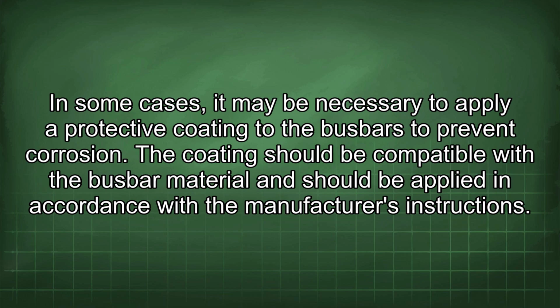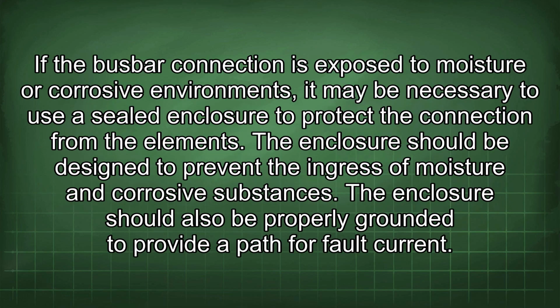In some cases, it may be necessary to apply a protective coating to the busbars to prevent corrosion. A coating should be compatible with the busbar material and should be applied in accordance with the manufacturer's instructions. If the busbar connection is exposed to moisture or corrosive environments, it may be necessary to use a sealed enclosure to protect the connection from the elements. The enclosure should be designed to prevent the ingress of moisture and corrosive substances. The enclosure should also be properly grounded to provide a path for fault current.